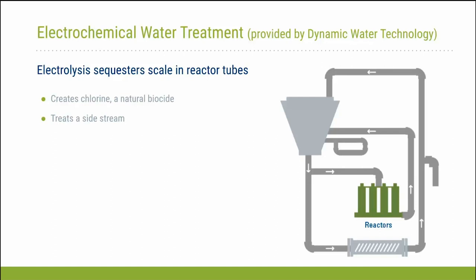This electrolysis process removes solids from the system to prevent or reduce scaling, which reduces blowdown and creates water savings. It also, during this process, creates chlorine, which is a natural biocide. So between reducing scale problems and introducing a biocide at the same time, water savings are seen, and chemical savings are seen as well. When we did the testing, we actually removed all chemical additives and turned those systems off completely. Again, the other thing we looked at was energy usage. We looked at pre and post energy usage for cooling towers and condensers as well.